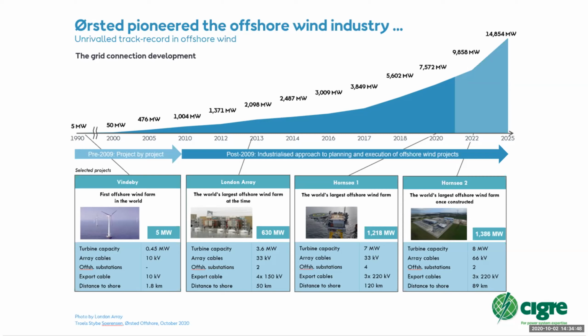The 1.2 gigawatt Hornsea 1, completed earlier this year, also connects wind turbines at 33 kilovolts, and uses 4 220 kilovolt offshore substations and 3 parallel export cables to land, about 120 kilometers, plus another 40 kilometers on land to reach a large dedicated onshore substation. And at the right-hand side is the next project.